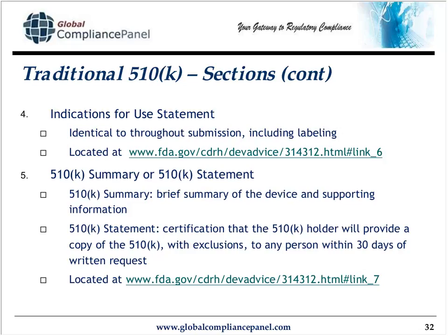The next section is either the 510K summary or the 510K statement. It is entirely up to you. Those of us who choose the 510K summary should give a brief summary, a couple of pages usually, of the device and the supporting information. Those of us who feel like we want to gamble a little bit will include a 510K statement, and it's a certification, and it says, you know what, within 30 days, I'm going to submit a copy of the 510K that's redacted, of course, with proprietary information pulled out.